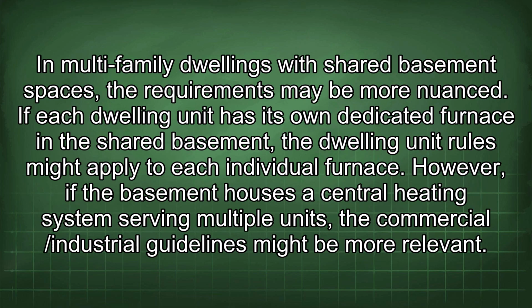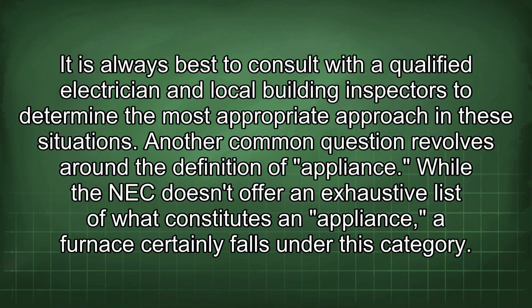In multi-family dwellings with shared basement spaces, the requirements may be more nuanced. If each dwelling unit has its own dedicated furnace in the shared basement, the dwelling unit rules might apply to each individual furnace. However, if the basement houses a central heating system serving multiple units, the commercial/industrial guidelines might be more relevant. It is always best to consult with a qualified electrician and local building inspectors to determine the most appropriate approach in these situations.